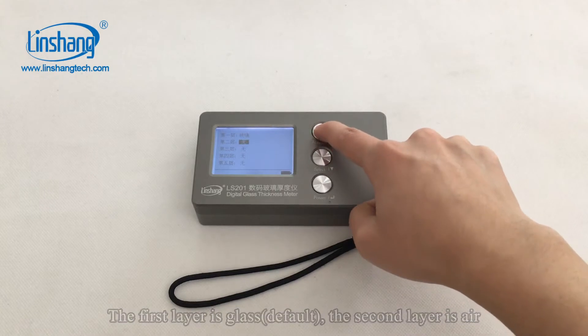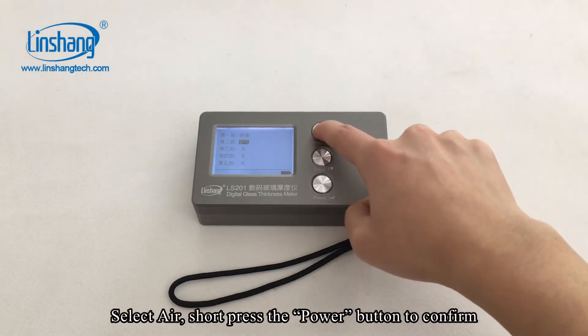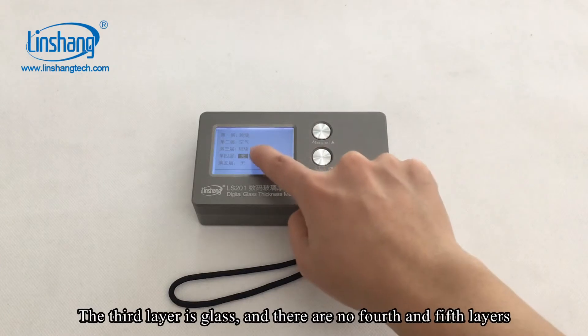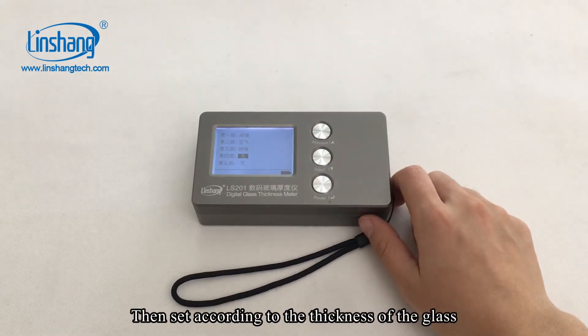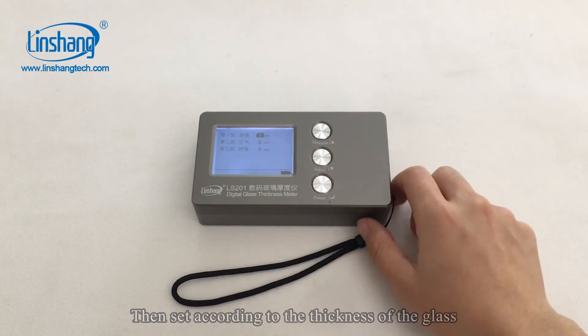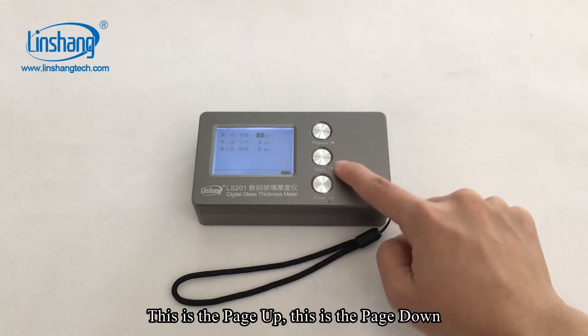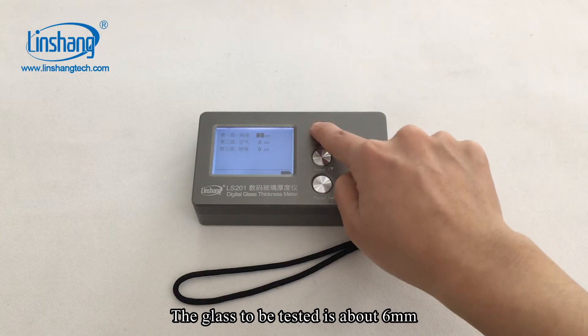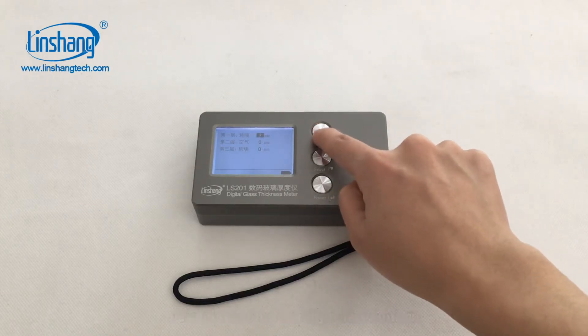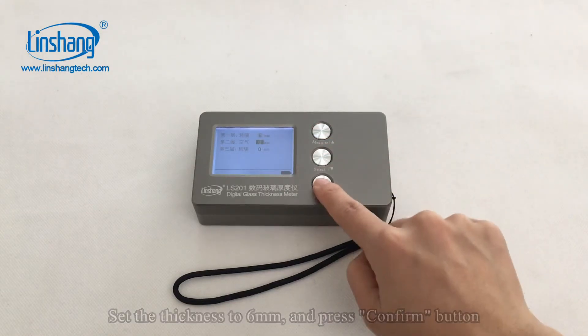The first layer is glass. The second layer is air — select L and short press the power button to confirm. The third layer is glass and there are no fourth and fifth layers. Then set according to the thickness of the glass using page up and page down. The glass to be tested is about 6 mm, so set the thickness to 6 mm and press the confirm button.